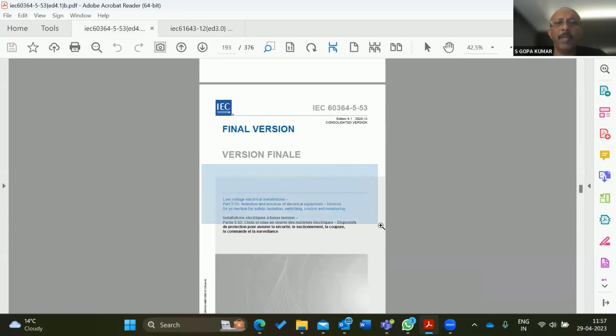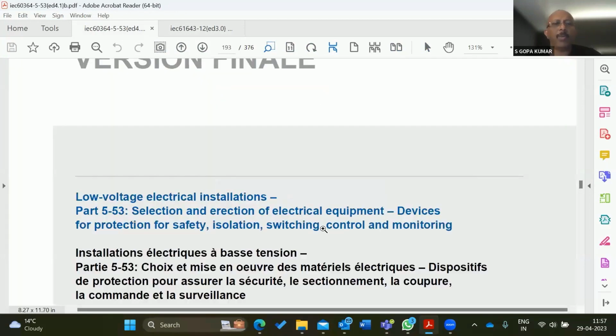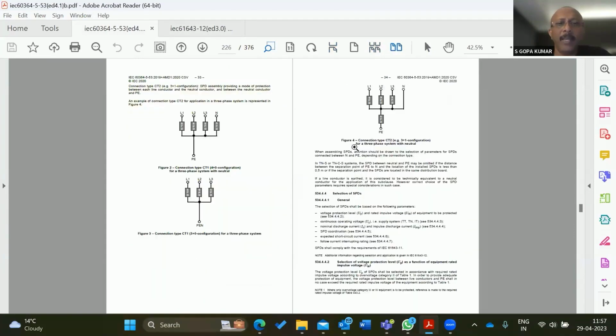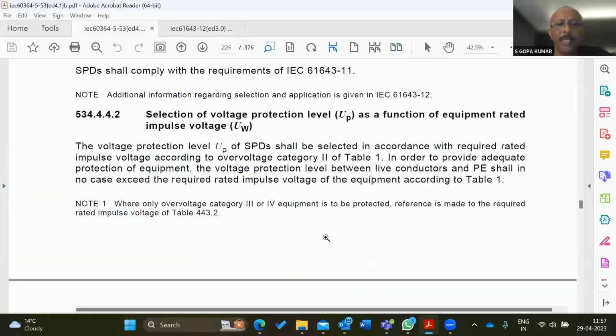One moment. Yeah, 553. This also talks about SPDs which have to be selected or used. The conditions can be used for selecting and erecting SPDs. I will just show some of the clauses which have to be taken care of while selecting and erecting an SPD. The first one, as you can see here, is selection of voltage protection level as a function of equipment rated impulse withstand voltage.